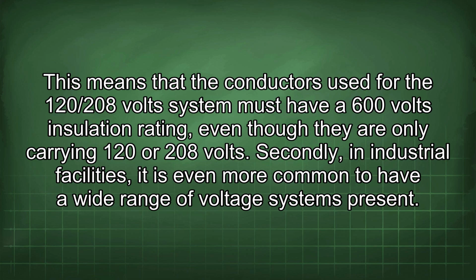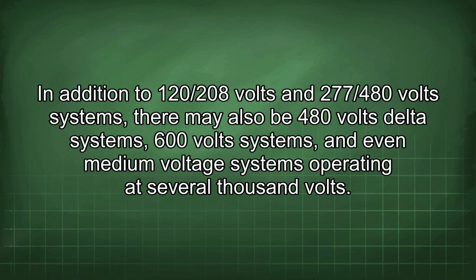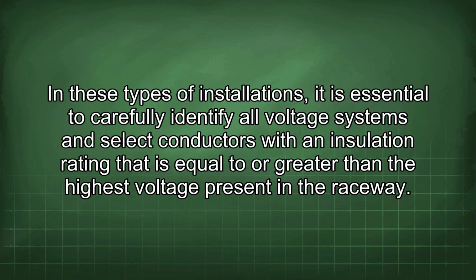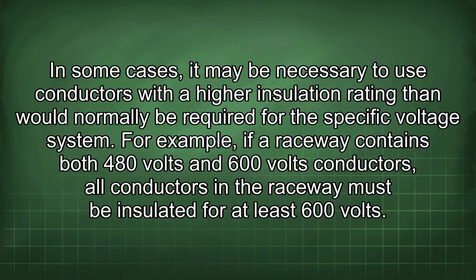Secondly, in industrial facilities, it is even more common to have a wide range of voltage systems present. In addition to 120/208 volt and 277/480 volt systems, there may also be 480 volt delta systems, 600 volt systems, and even medium voltage systems operating at several thousand volts. In these types of installations, it is essential to carefully identify all voltage systems and select conductors with an insulation rating that is equal to or greater than the highest voltage present in the raceway. In some cases, it may be necessary to use conductors with a higher insulation rating than would normally be required for the specific voltage system. For example, if a raceway contains both 480 volt and 600 volt conductors, all conductors in the raceway must be insulated for at least 600 volts.